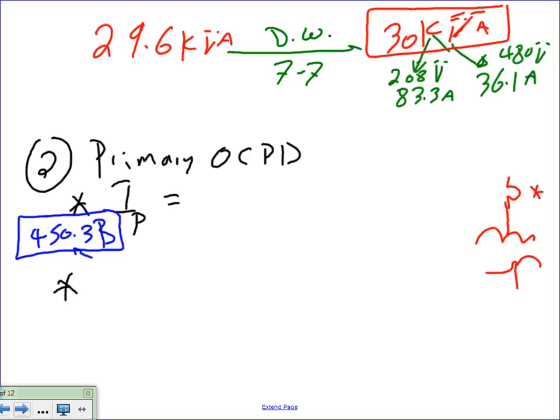So what I did for the I primary, guys, you do one of two things. You take the 30K, divide by 1.73 times 480, and that should get you the same amount, 36.1 amps. Does that sound familiar from what we got from DeWalt, give or take? Either you do the calculation, I like you to do the calculation, or you can grab it from DeWalt. That's the first thing to do, find the full load current on the primary side. And what we're trying to size here, Nick, is the overcurrent device that protects the transformer.